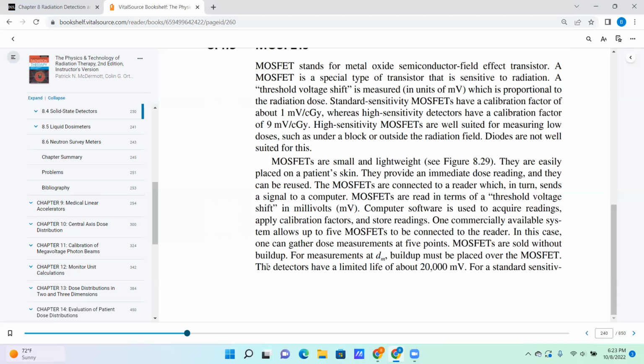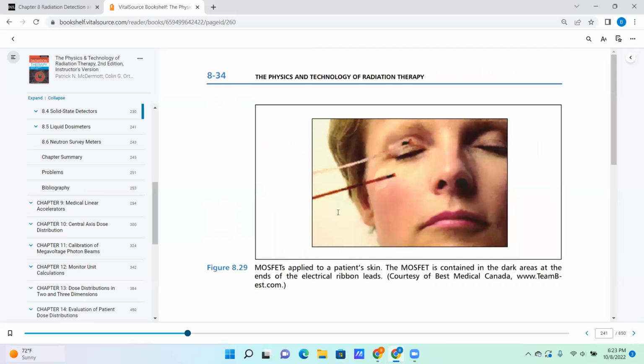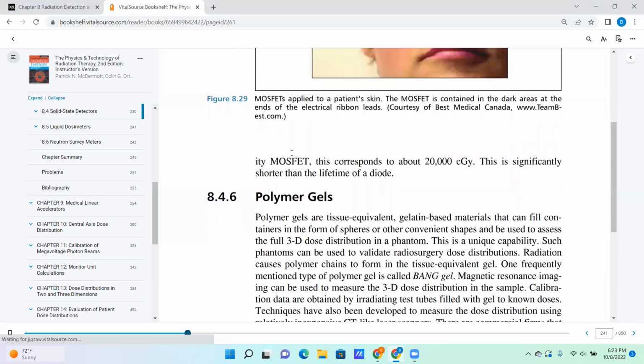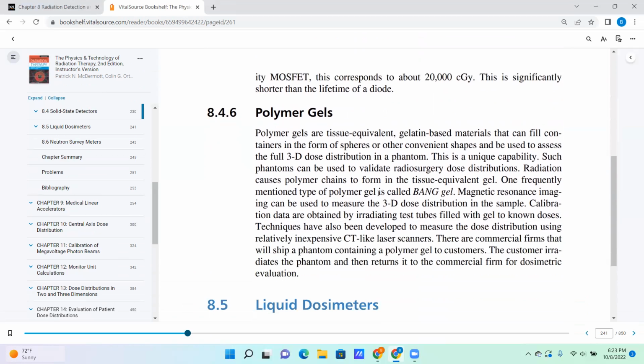MOSFETs are sold without buildup. For measurements at Dmax, buildup must be placed over the MOSFET. The detectors have a limited life of about 20,000 millivolts. For a standard sensitivity MOSFET, this corresponds to about 20,000 centigray. And that's considerably shorter than the life of a diode.